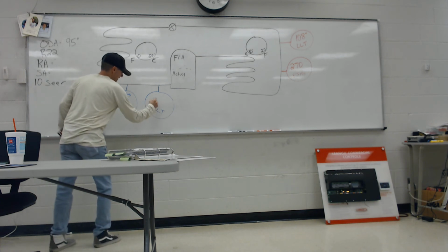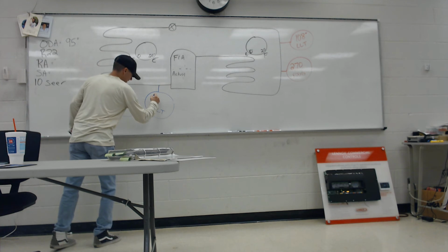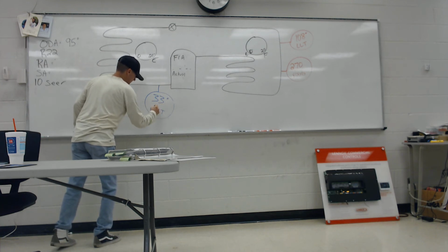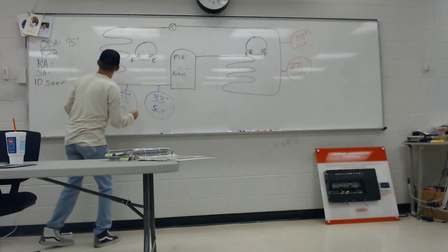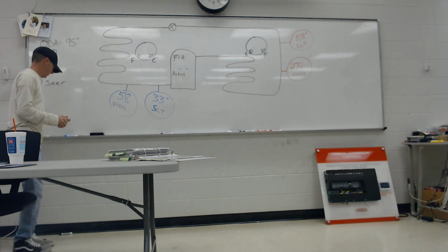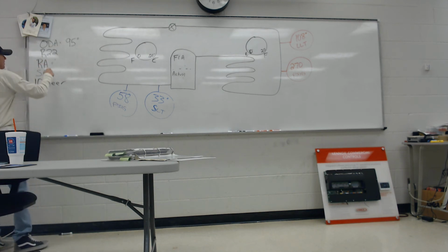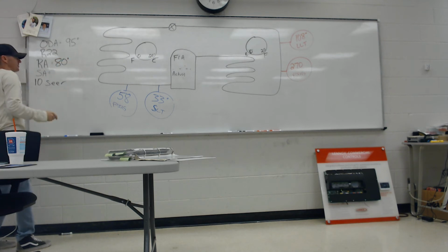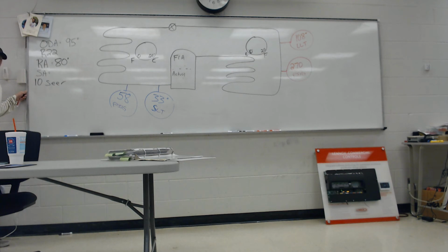And then my suction line temperature is 33 degrees. Return air is 80. We gotta get this thing cooled down so they can get back to work and start making money again. Plus we gotta rip 5 other units off the roof. We've gotta get this one fixed and cooling before we can start pulling the other ones off the roof.